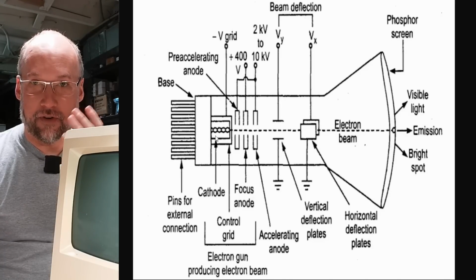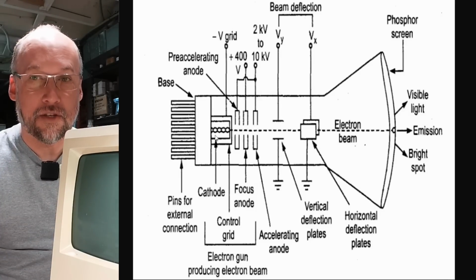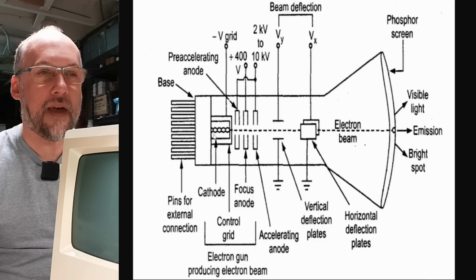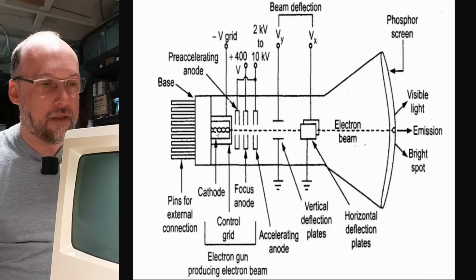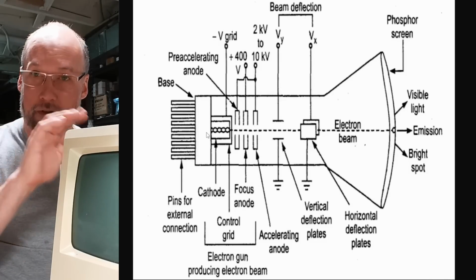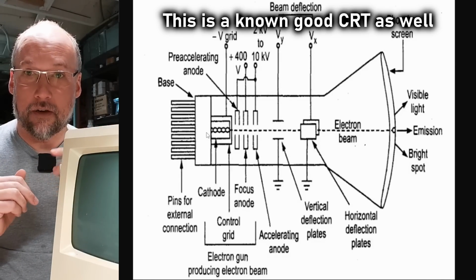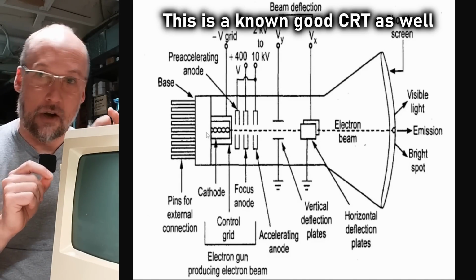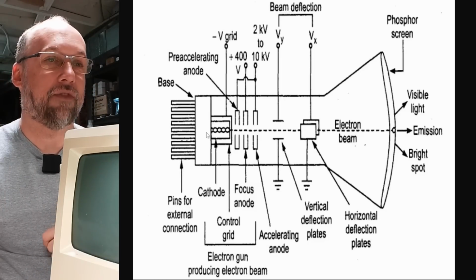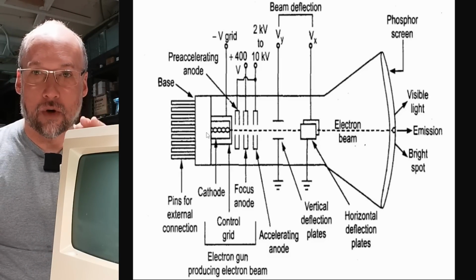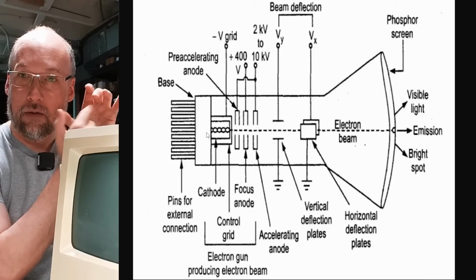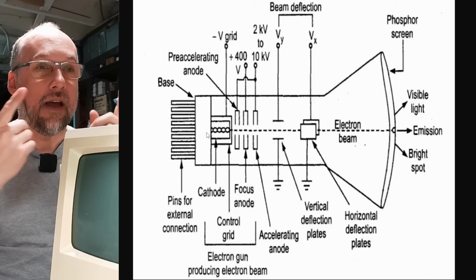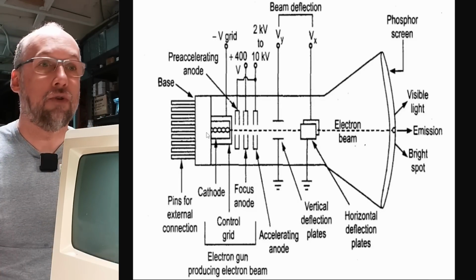As I mentioned earlier, for the cathode to work and have actual emissions of electrons, it needs to be warmed up, and that's the heater or the filament that does that. Now, I did check, and there is 12 volts on the heater on the CRT, so we know that's good, and I'm seeing a little bit of a glow. I just didn't quite see it at first until I turned off the lights. So we know the cathode is working because we saw the signal on the oscilloscope of what the Macintosh is trying to display, and I know the heater is working. So those two components are good.